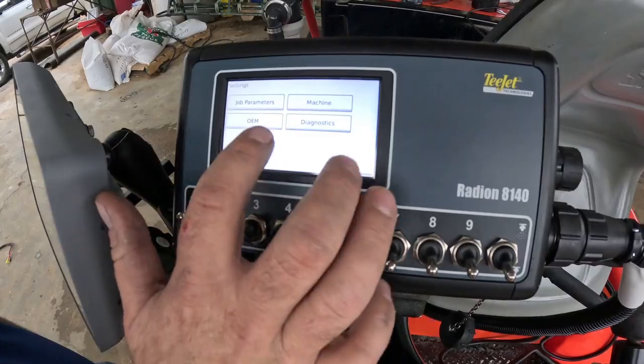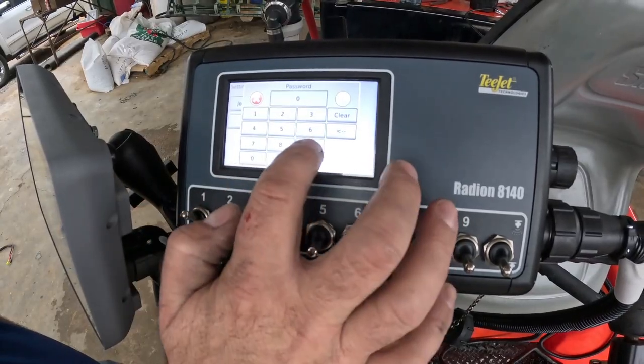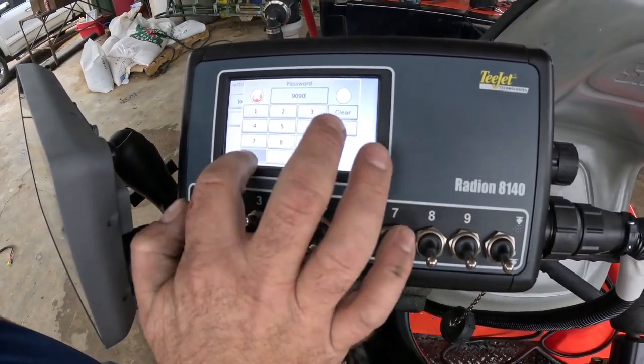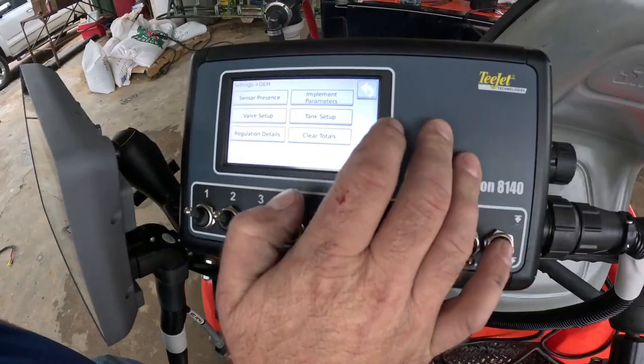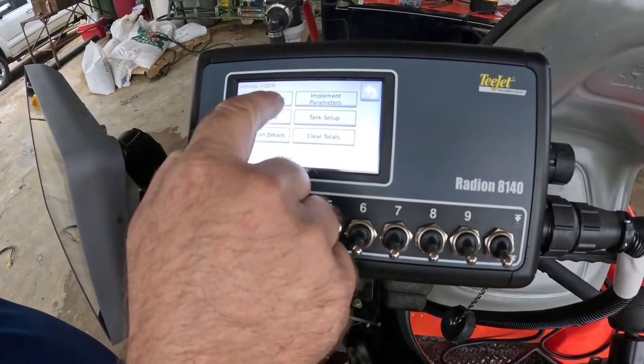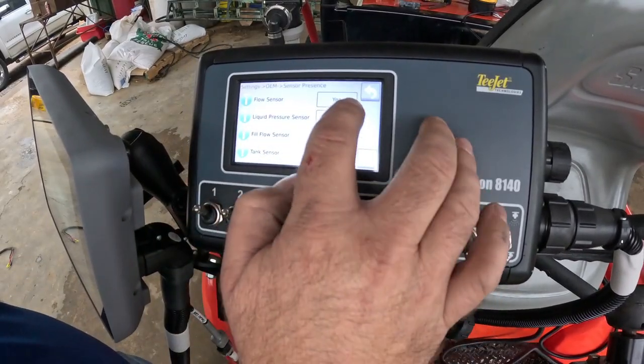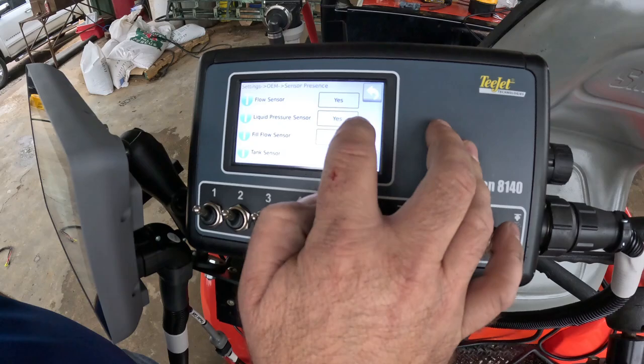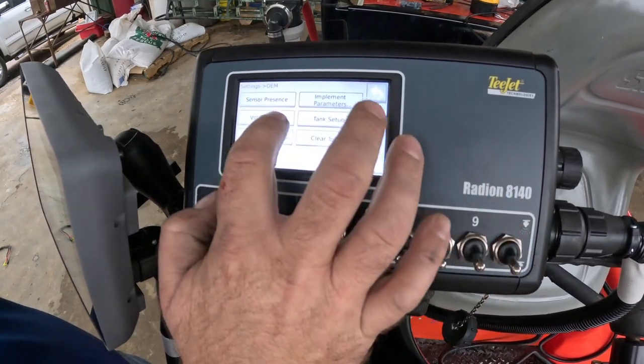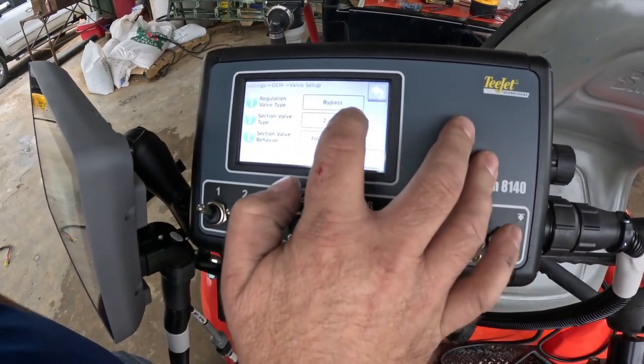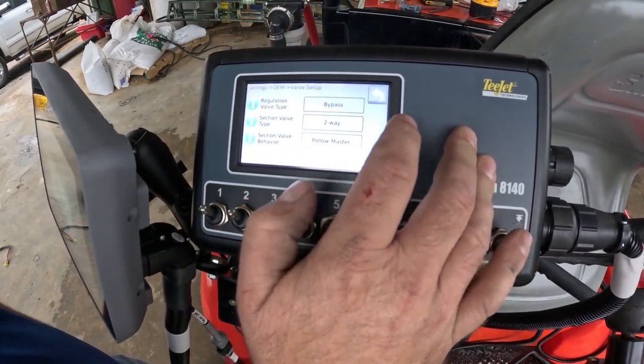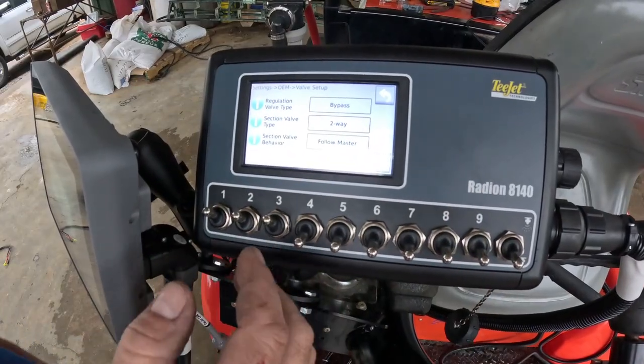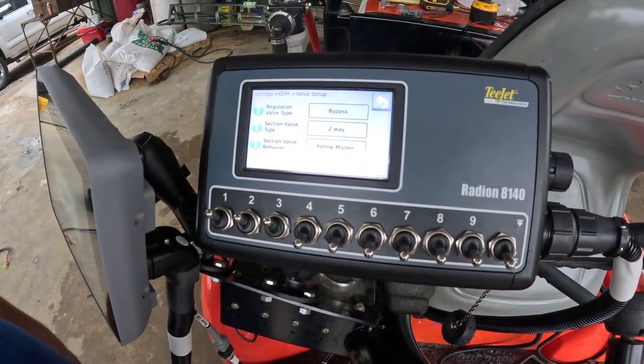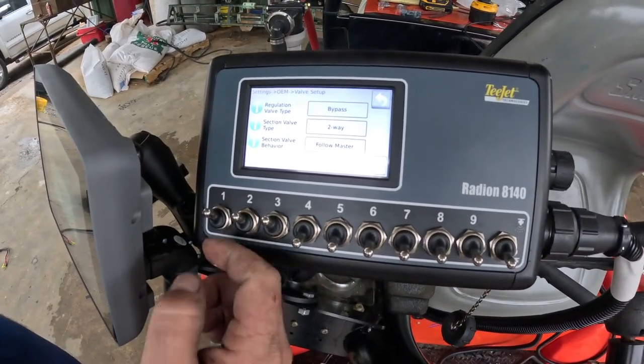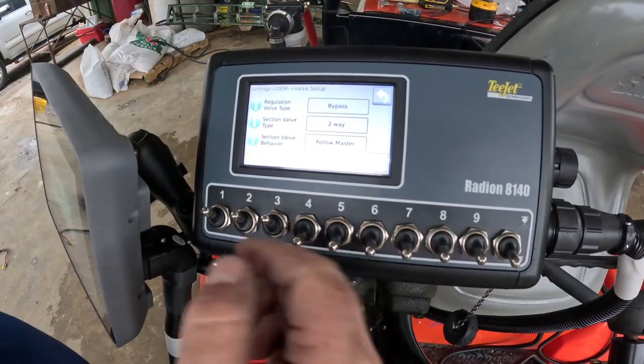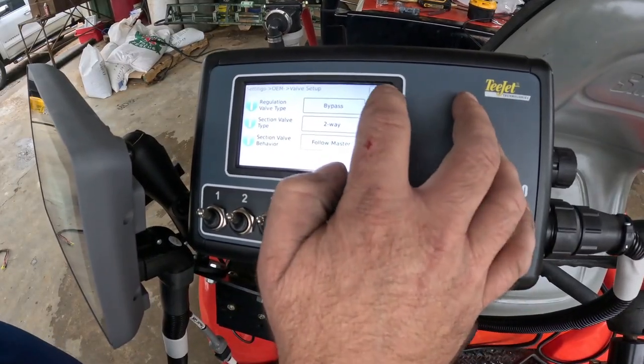The first thing we're going to do is go into OEM. You need a password, that's 9090. Hit the check mark. And then we're just going to go through this list one at a time. So sensor present, we have a flow sensor and a pressure sensor. Our valve is a bypass valve. It's a two-way bypass valve. Section valve behavior is follow master. So if I turn the master switch off, it turns all of my section valves off as well. That's what follow master does, which is the best way to run it.